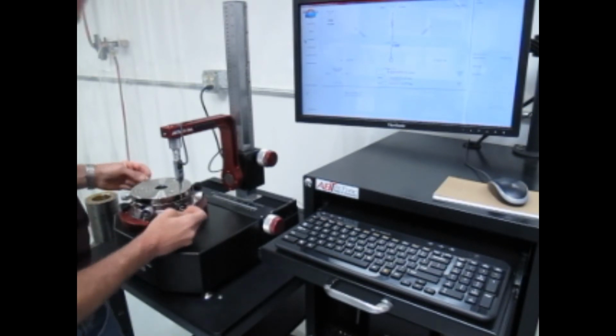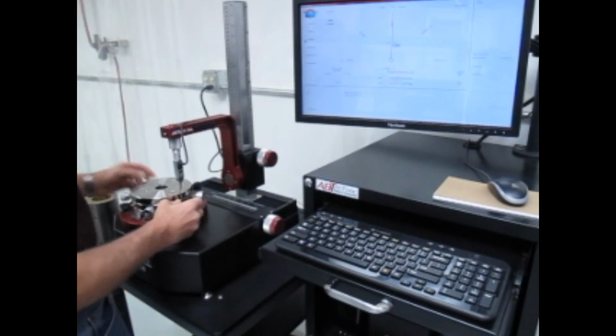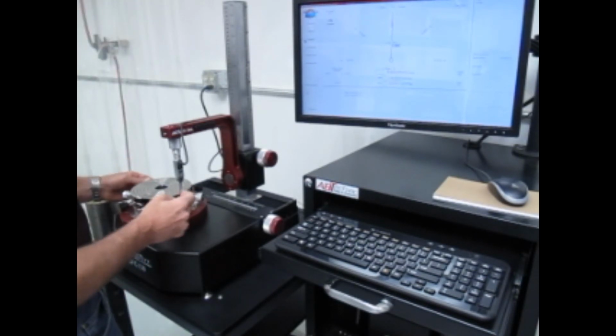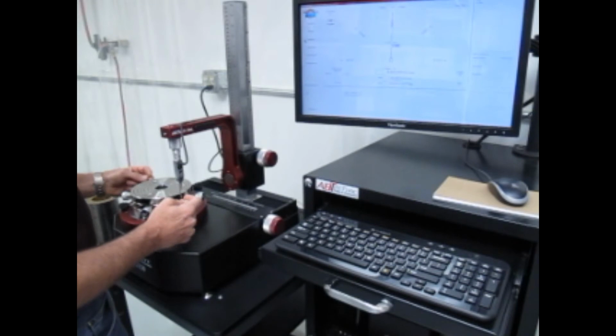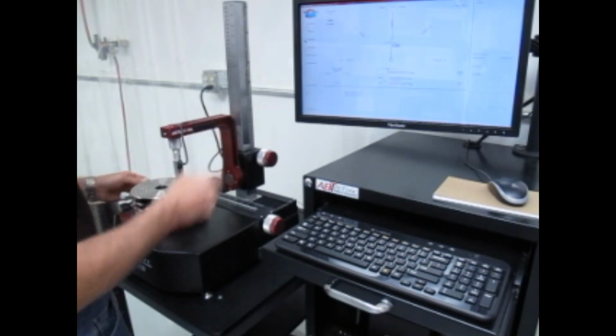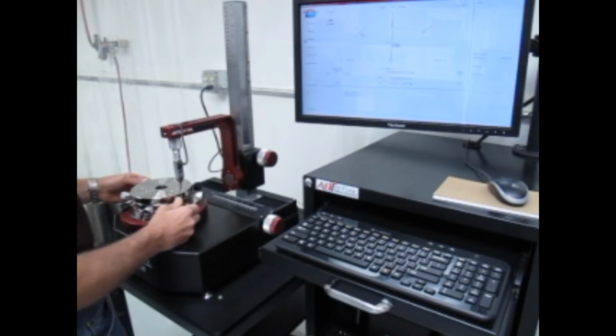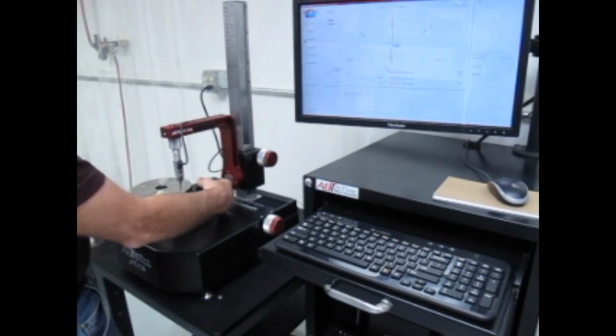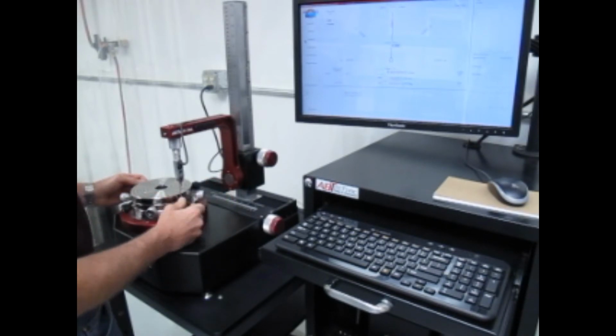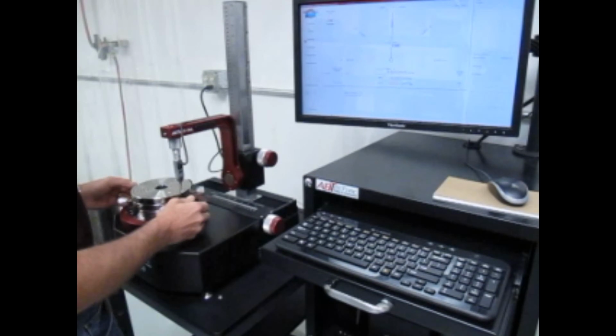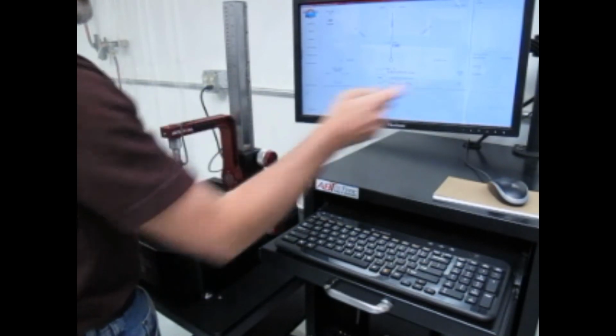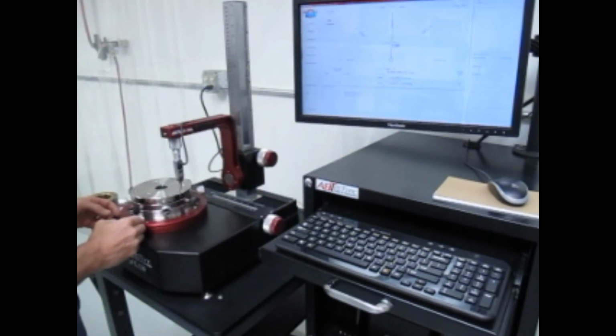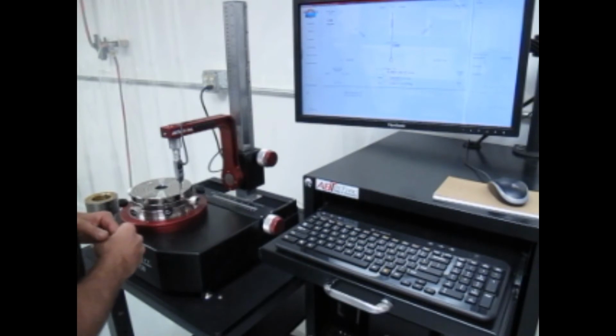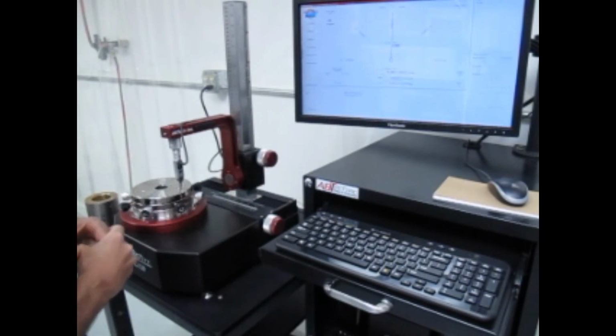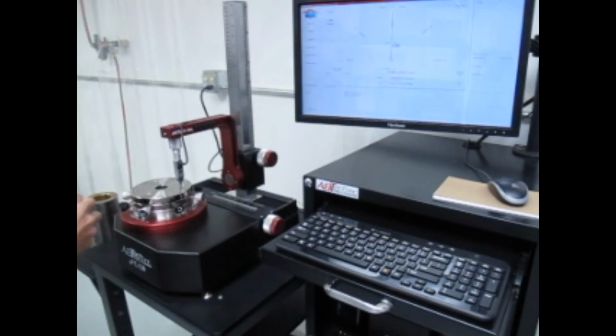So this set of knobs, which is the CY, move it 180 degrees so that the other CY knob is in line with that, and my indicator should come back to the same location. Then I turn to the 90 degrees from there to the CX knobs and do the same thing. And I've got good repeatability. I'm going to clear the TIR and see what I have. I am now aligned. Max TIR is about a 10,000ths of an inch.